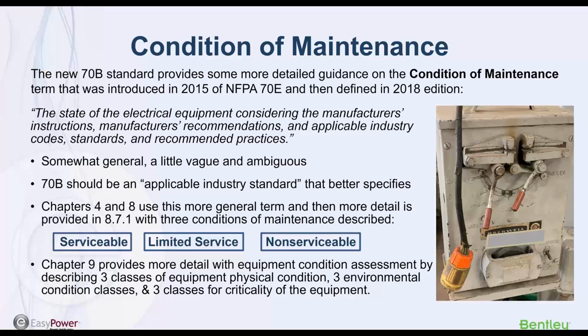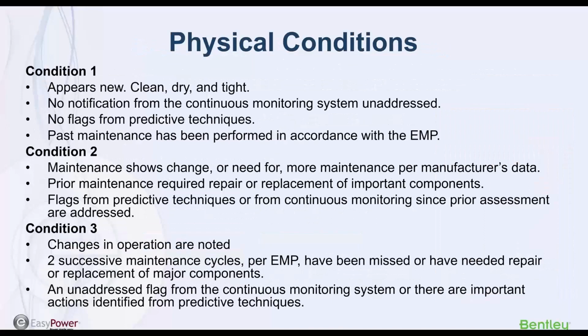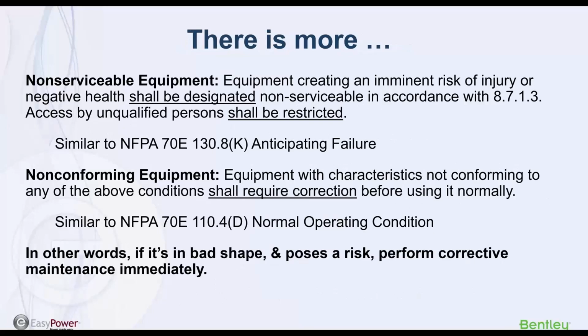You have multiple classes of physical condition, classes of environmental condition, and classes for criticality of the equipment. For physical conditions, you have condition 1, 2, and 3. Condition 1 means the equipment is basically good - there's no reason to believe it requires any special reaction, so whatever your maintenance plan says to do on a normal schedule is probably enough. Condition 2 means you're seeing a change - something may be needed, probably in the shorter term rather than longer term. Condition 3 means serious changes, and you probably need to change what you're doing or the frequency with which you're doing it. Non-serviceable equipment means you have an imminent risk.